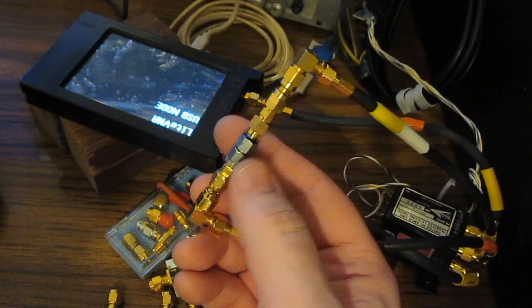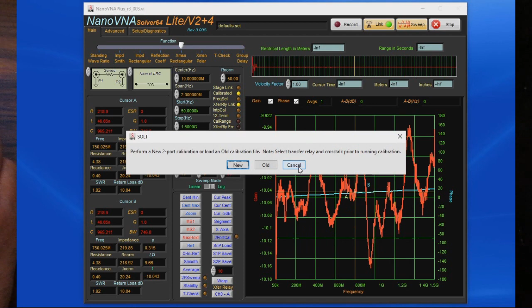This is looking at the data sheet for this particular part. This is a 10 dB part, so this is rated for plus or minus 0.5 dB, so at least up to 1.5 gigahertz. This device is well within the manufacturer's rating. So let's go ahead and we'll disable our calibration. We do that by selecting 2-port cal, and we'll select cancel. You can see the calibrated LED is turned off.